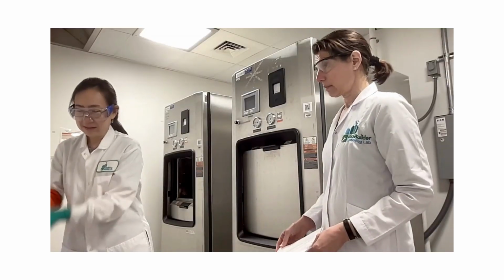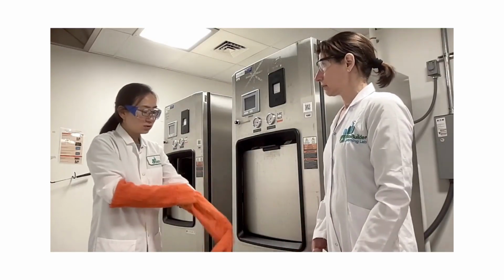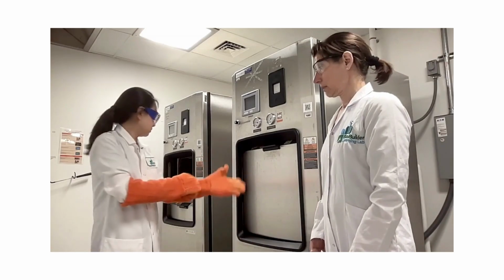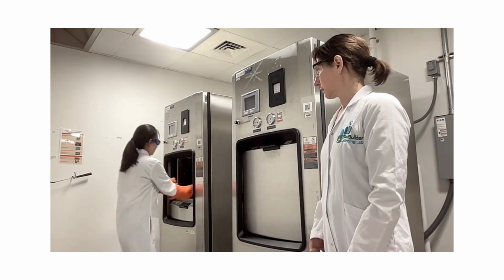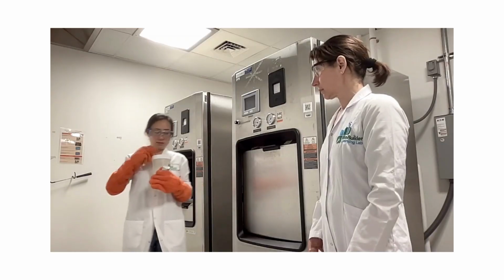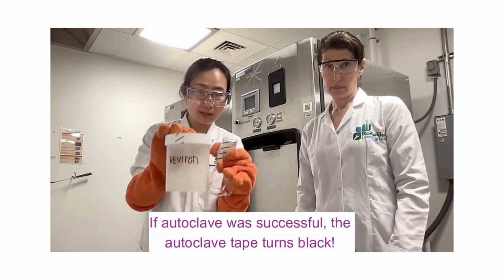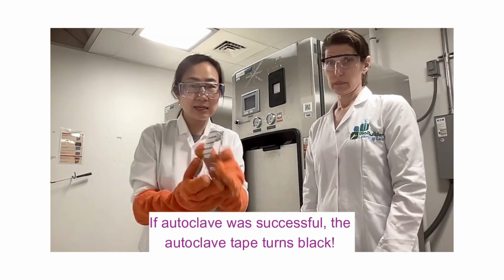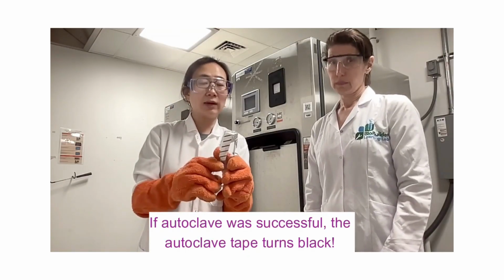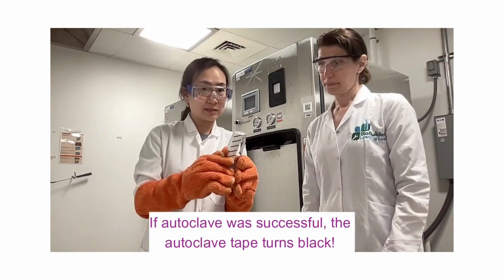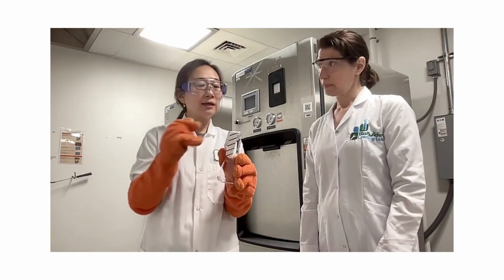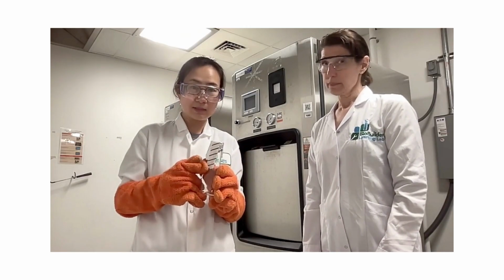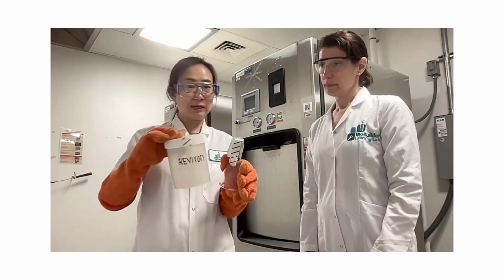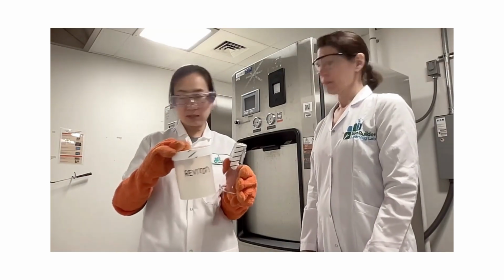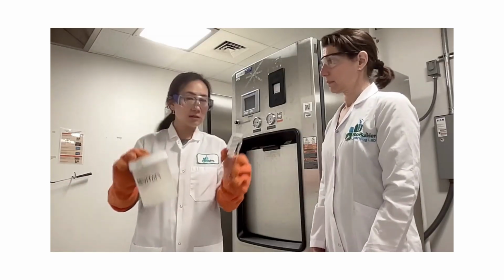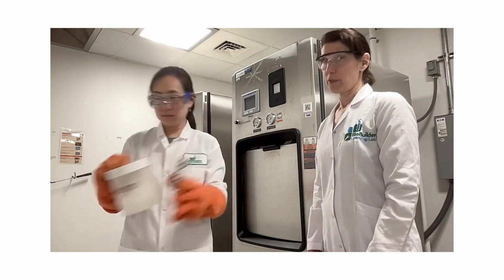And then what does it look like at the end? How do we know it's done? You know it was properly autoclaved when the autoclave tape turns to black stripes like this. That indicates that it reached the correct temperature as well as the pressure, and for the minimum amount of time needed. If this tape doesn't turn black like this, that means that your autoclave failed and that the items you wanted to sterilize are not sterilized, meaning bacteria, spores, germs are not dead. So you'll have to do it again.